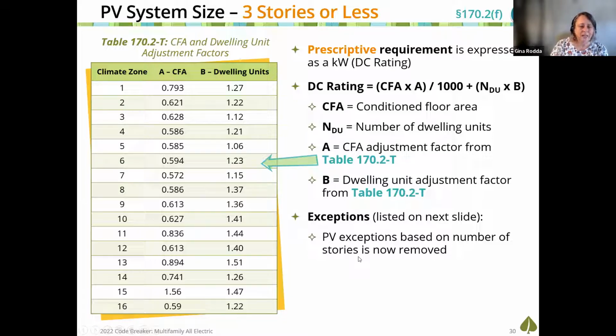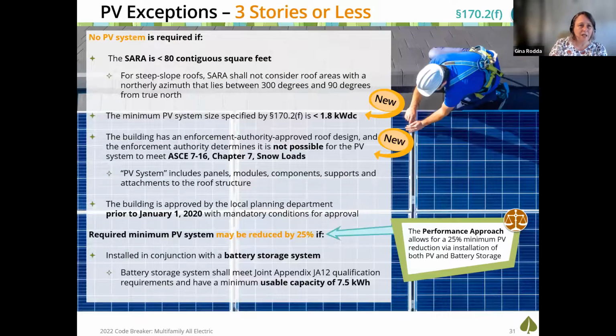Now, there was an exception saying PV is not required for 4 stories or greater. That exception has been removed because PV is required for those buildings now. They have tweaked the exceptions slightly. We still have the exception saying if you can show with an approved solar access tool that you don't have at least 80 contiguous square feet in one place with annual solar access exceeding 70% over the entire year, you're exempt from the energy code requirements of PV. That's when you'd have to meet the solar ready requirements instead.